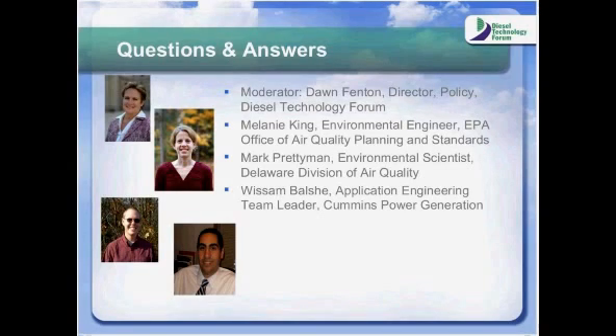Yes. Okay. Another one here, and let me just read it for you. For the 50 hours of non-emergency runtime allowed for emergency stationary engines, what would be an example of such a runtime if they are not allowed to be run as part of a peak shave application? For example, would a storm avoidance scenario be permitted? You're talking about, say, a storm is forecast and you want to turn on your engine so that you don't lose power? Yes, that would be something that could be part of that 50 hours for non-emergency operations.